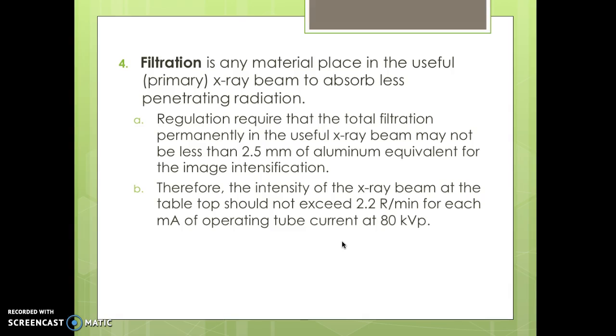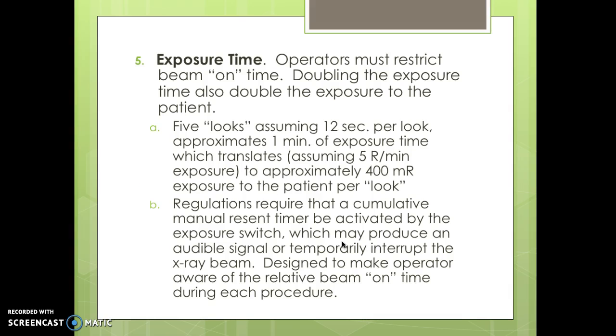Exposure time: the operator must restrict the beam-on time — doubling the exposure time doubles the exposure to the patient. If you take five looks at approximately 12 seconds per look, that's roughly one minute of exposure time, which translates to about 5 R per minute, or approximately 400 mR exposure to the patient per look. Regulations require that a cumulative manual reset timer be activated by the exposure switch, which may produce an audible signal or temporary interruption of the x-ray beam, to make the operator aware of beam-on time.